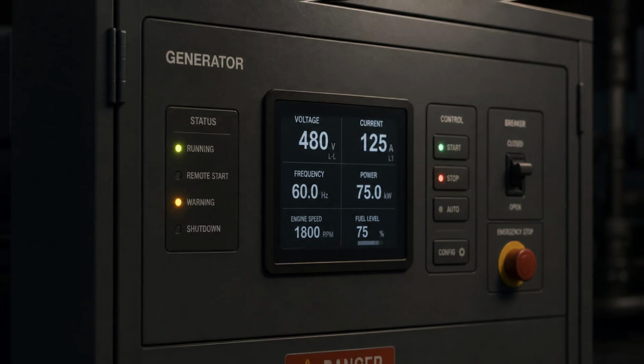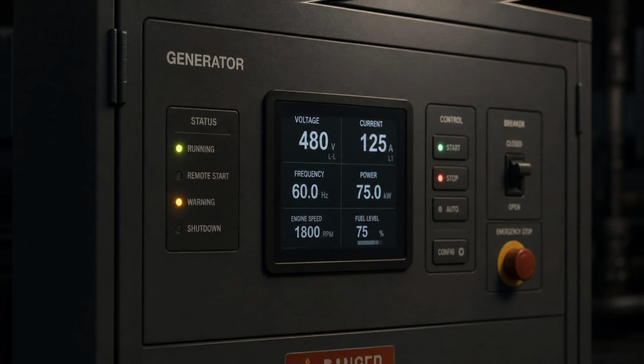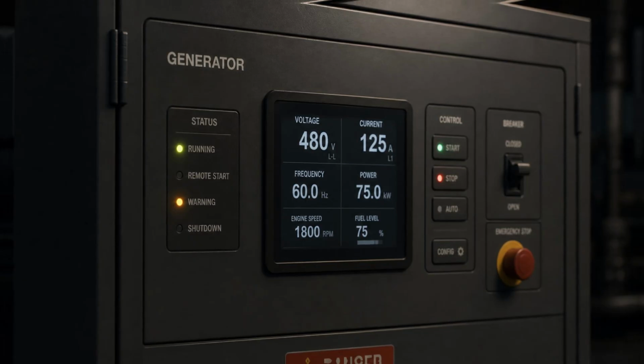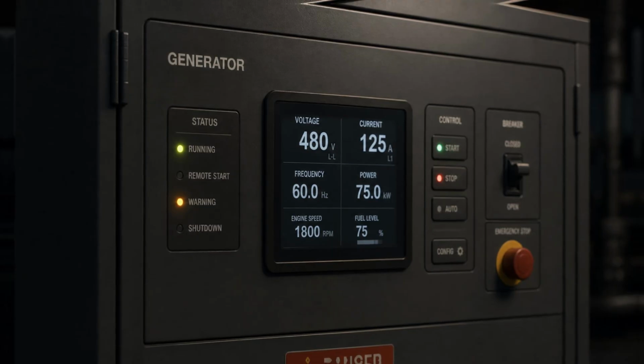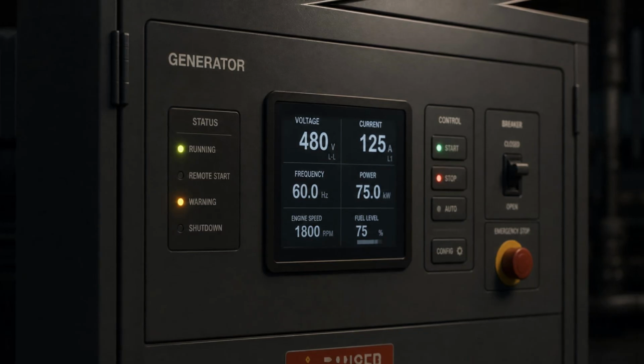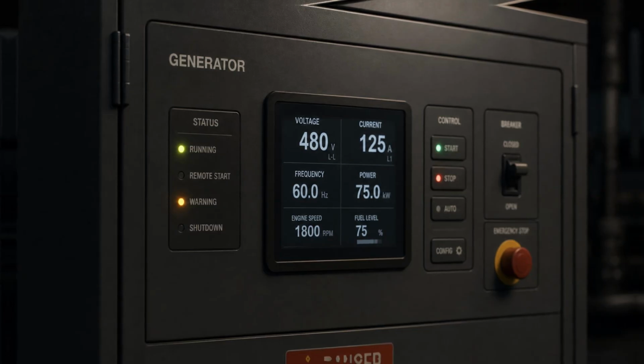It is designed to carry it long enough for the generator to start, long enough for the transfer switch to complete its handoff, long enough for the critical equipment downstream to receive generator power before the batteries are depleted. In most commercial applications, UPS systems are sized to provide somewhere between 5 and 30 minutes of runtime, depending on the load and the design intent. Some hospital and data center applications call for longer run times. Some smaller installations need only a few minutes.